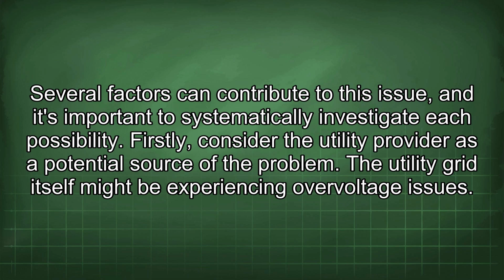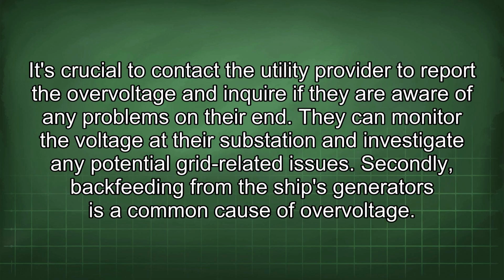Firstly, consider the utility provider as a potential source of the problem. The utility grid itself might be experiencing overvoltage issues. It's crucial to contact the utility provider to report the overvoltage and inquire if they are aware of any problems on their end. They can monitor the voltage at their substation and investigate any potential grid-related issues.